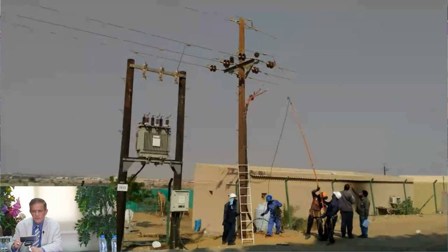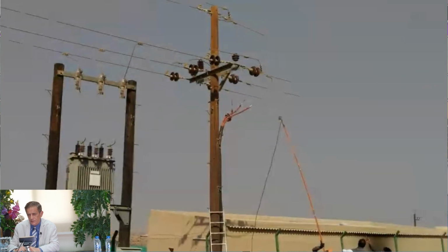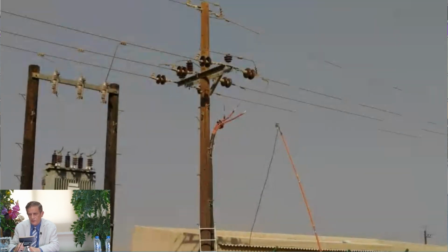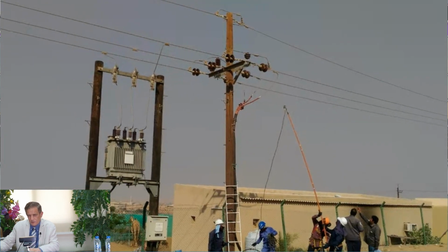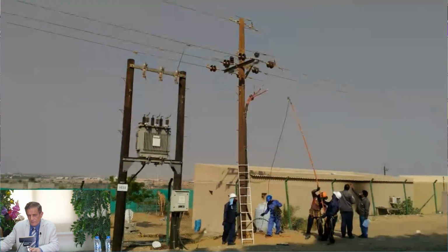This charge is available even if the line is open circuited. So normally, before doing any maintenance, switching, connection or termination on a transmission line, we discharge it, as you can see here in the picture - they discharge the line even though it's open circuit. There is a charge stored in this transmission line, so this is very important: something dangerous is present on the line even if it's open circuited.